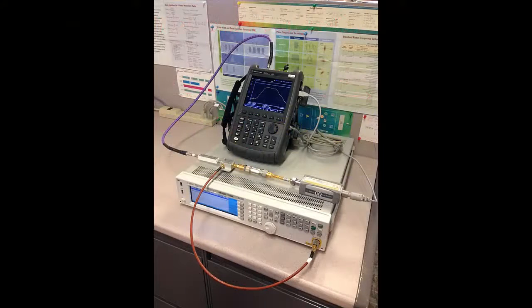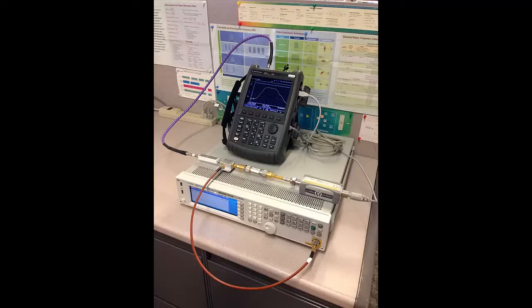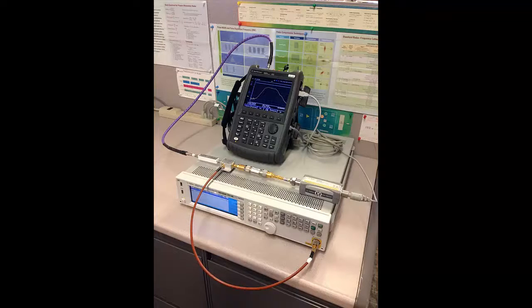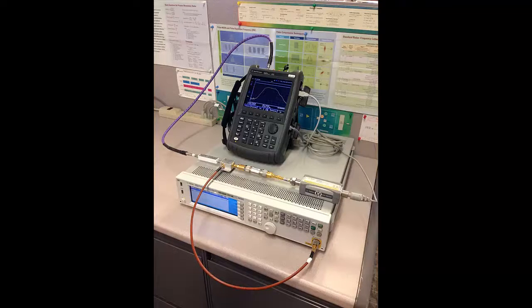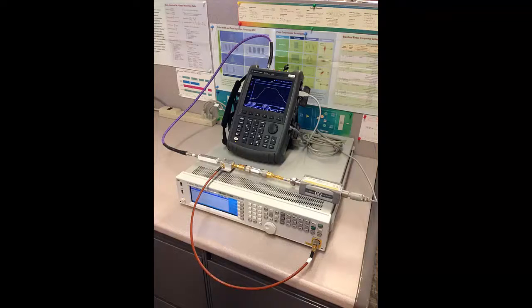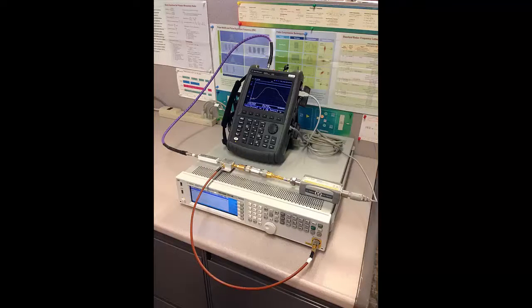In this picture of my test setup, we have the N9918A cable and antenna tester, which includes Option 302 for Keysight USB power sensor support, as well as Option 208, which provides frequency offset using power sensor measurements. Be aware that both Option 302 and 208 are required for this measurement.